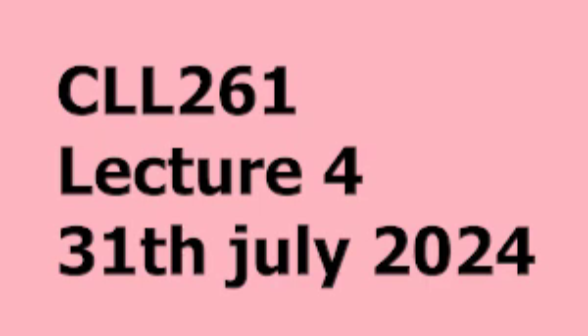Okay, alright. So you can convert this melt index value to the concentration by using a model, isn't it? This model could be a regression model, could be a machine learning model, whatever, or it could be simply an empirical model. You can use that here to convert this melt index value to a concentration, and then you can see that this Ca is the unmeasured variable here. But we are estimating the value of Ca indirectly by measuring a secondary variable, which is melt index.